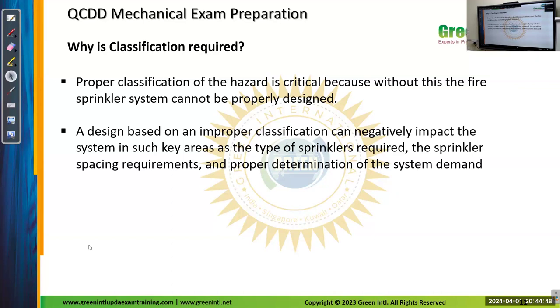That depends. That's why proper classification of the hazard is critical, because without this, fire sprinkler systems cannot be properly designed. A design based on an improper classification can negatively impact the sprinkler systems in such key areas as the type of sprinklers required, the sprinkler spacing requirements, and proper determination of the system demand. Self-explanatory, right?